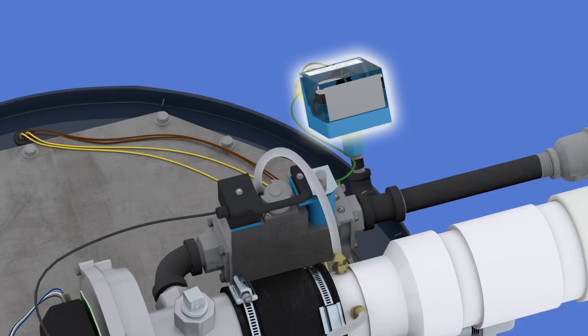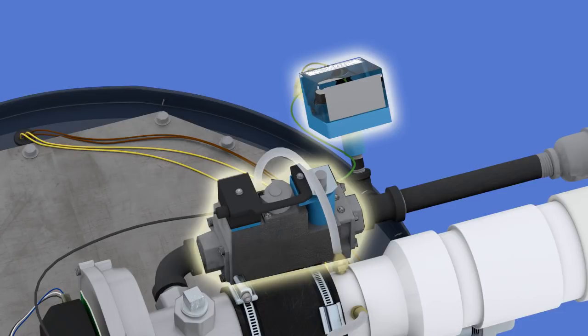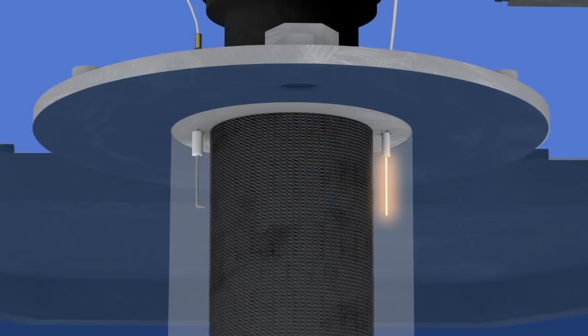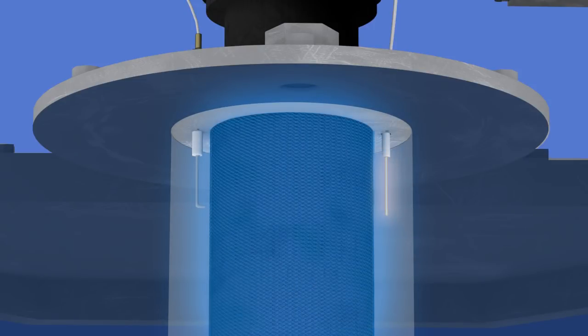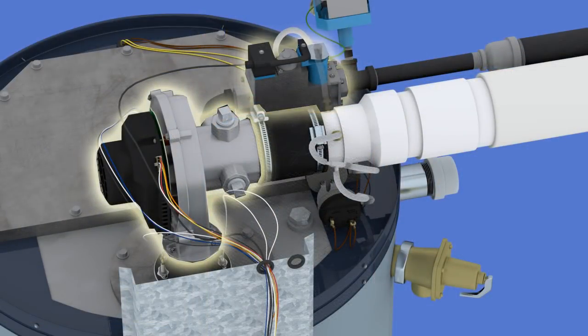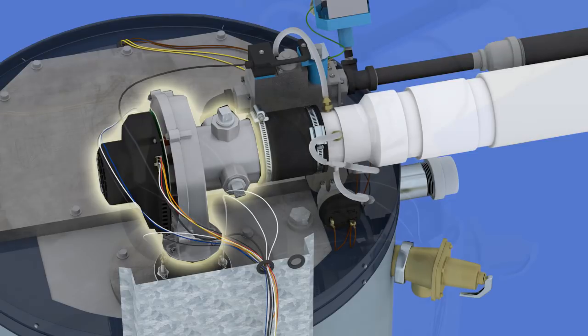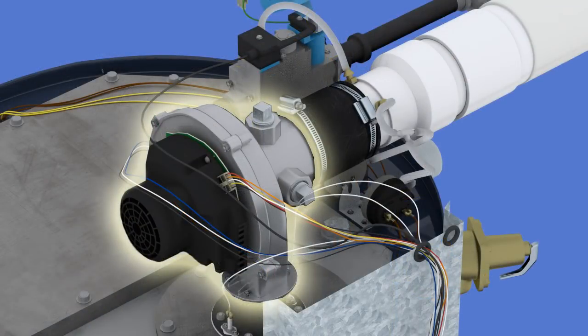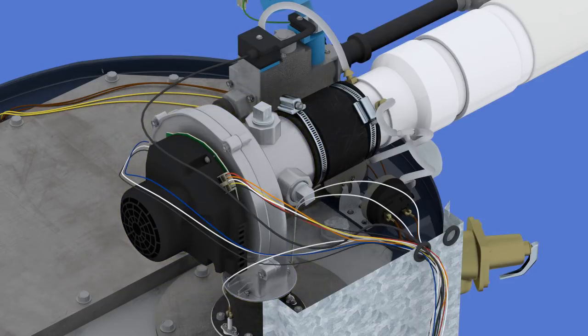If the normally open low gas pressure switch is closed, the gas valve is energized. Then the gas valve opens. Trial for ignition begins and the igniter stays energized for an additional 3 seconds. If a flame is established within 5 seconds, the burner is in run condition. The burner remains on and modulates based on sensor value versus temperature set point. Once the call for heat is satisfied, the gas valve de-energizes and closes. The blower will continue to run for a 25-second post-purge, after which the blower is de-energized and the system goes into standby mode.